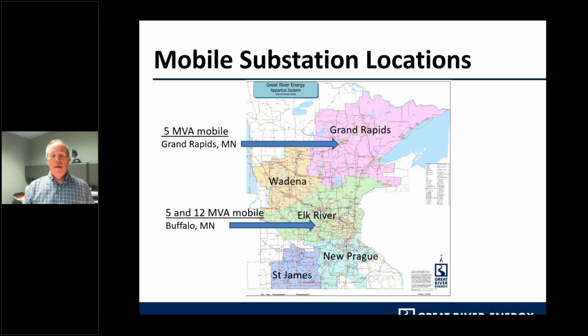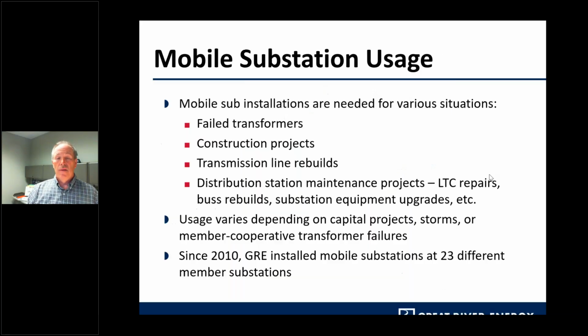Mobile subs are used for various situations. If there's an emergency, like a failed transformer, GRE will dispatch the appropriate technicians to install the mobile sub. This also requires truck drivers to move the mobile, line technicians for switching and hooking up the mobile sub, apparatus techs to check the mobile sub operation and verify that all settings are correct for the distribution sub it's installed at. The relay and meter technicians can remotely call in to verify settings and operations. We can also set up crews for 24/7 operation when we need to get the mobile installed in a safe and timely manner to get our customers back online as soon as possible.